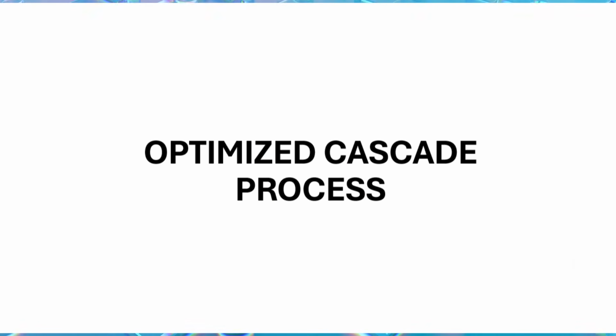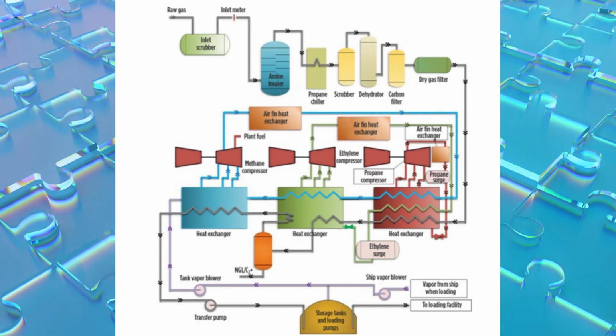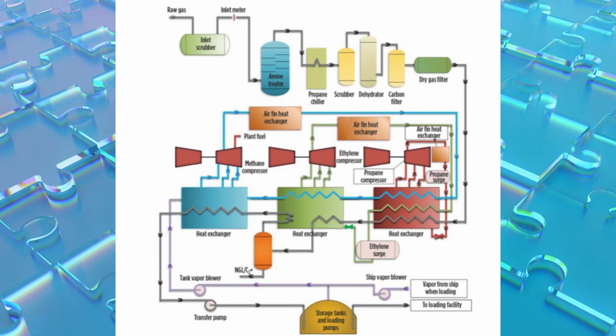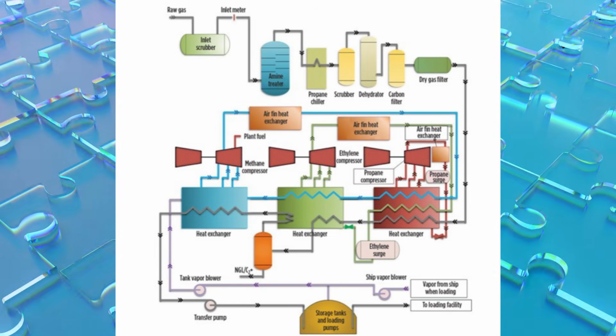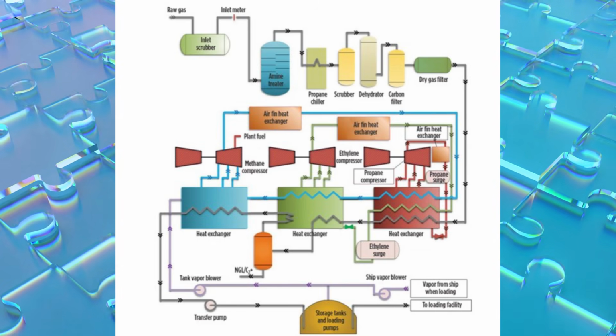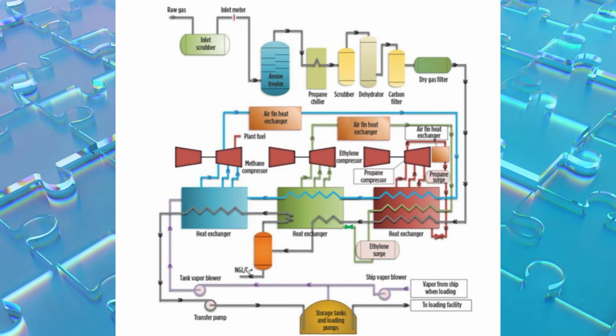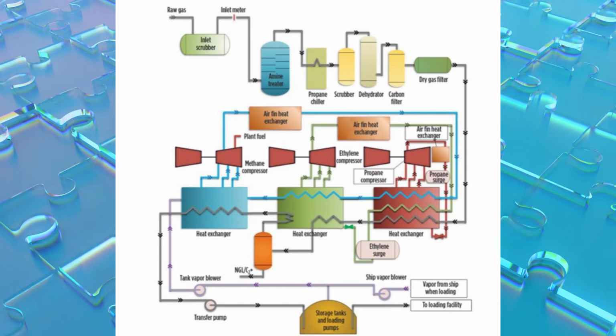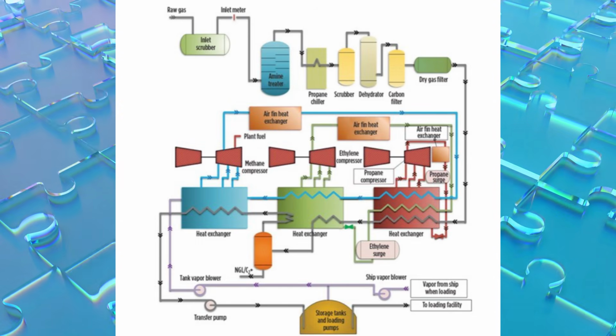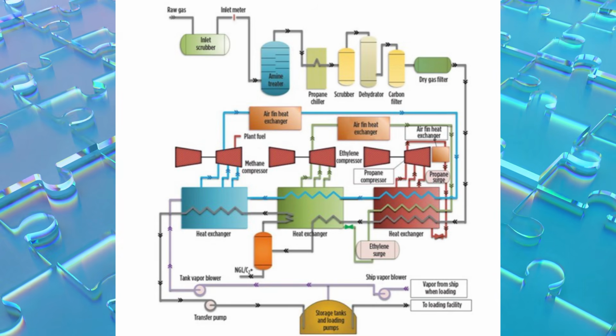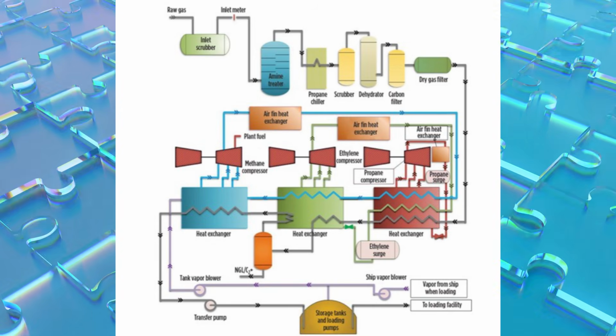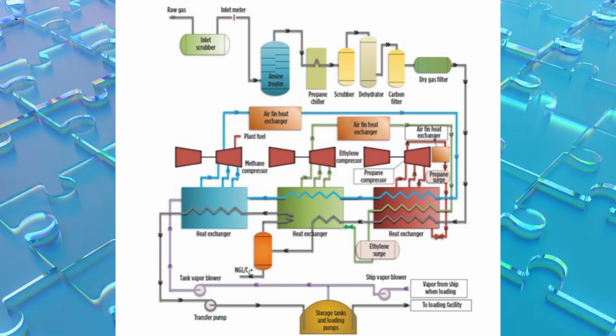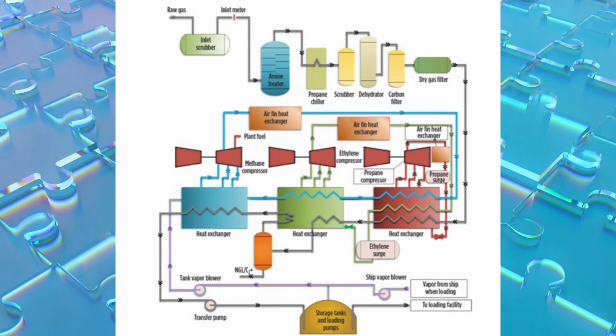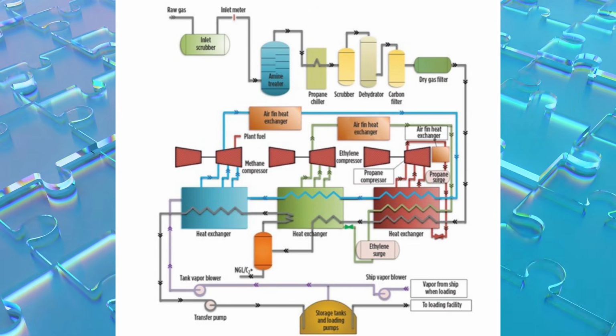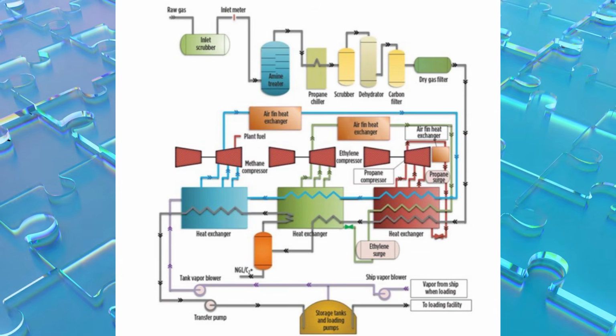The optimized cascade process, OCP, is a simple and reliable technology. A process flow diagram for the OCP is shown here. In this process, 3 pure component refrigerants, namely propane, ethylene, and methane, are used at different pressures during the refrigeration and liquefaction processes. Centrifugal compressors are used for the circulation of these refrigerants and cooled within a series of brazed aluminum vertical cold boxes. The power is supplied through frame 5 gas turbines.